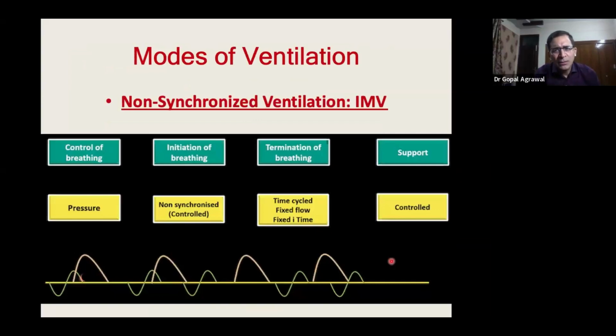So coming to the basic mode of ventilation, intermittent mandatory ventilation, where the baby breathes on its own and the machine delivers a fixed number of breaths at fixed intervals, irrespective of whether the baby is breathing or not. And it doesn't try to synchronize the baby's breath with the machine's breath. So there is no synchronization. Here the control of breathing is pressure limited. Initiation is by the machine, so it's not synchronized with the baby. Termination is again time cycled, fixed time and fixed flow.